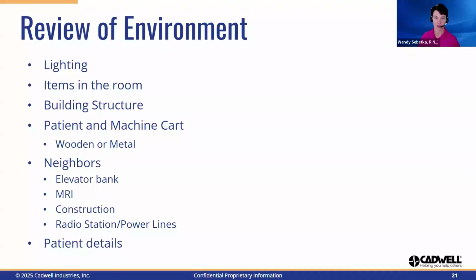To help with identifying the source, we should do a quick mental review of our environment, making note of anything that may have changed. Changes that can be seen visually, such as a plugged-in heating pad or a cell phone on the charger, are of course the easiest to recognize, but many environmental factors are unable to be seen. A fluorescent light that's not securely connected or the new heater that was added to the office next door are also culprits of noise and should be thought about. When troubleshooting ongoing intermittent issues, it's especially important to make note of the overall environment, not only being aware of the items in the exam room, but also adjacent areas and even structures that surround the general area of your building. Included in the overall review are the details regarding the patient.